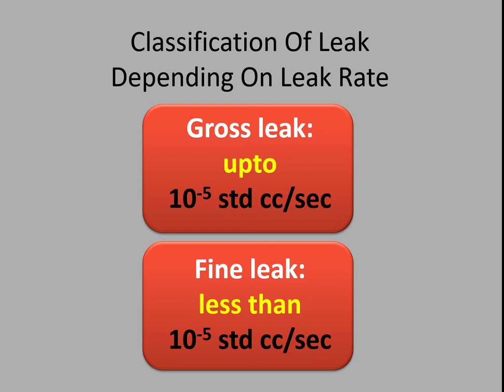On the basis of leak rate, leak is classified into two categories: gross leak and fine leak. Up to 10 raised to the power minus five standard cubic centimeter per second is classified as gross leak, and less than 10 raised to the power minus five standard cubic centimeter per second is classified as fine leak.